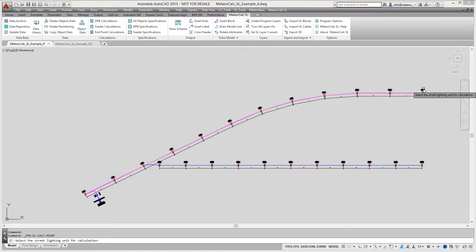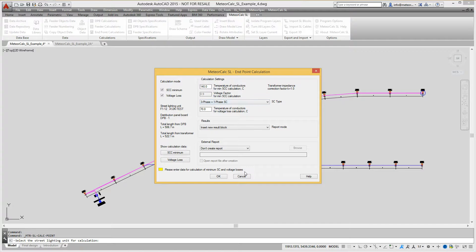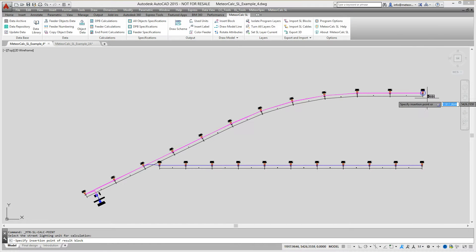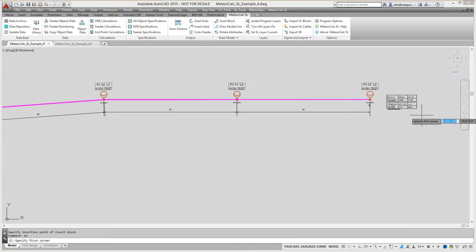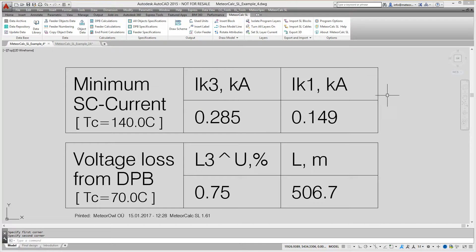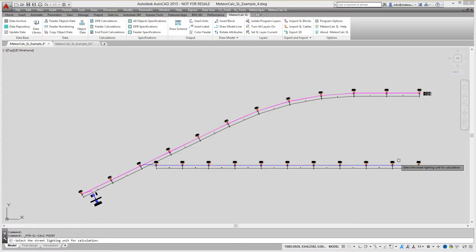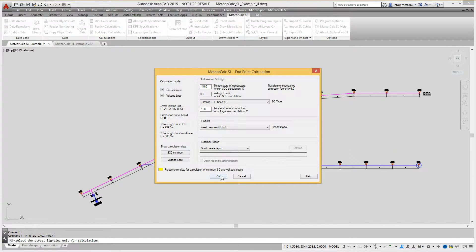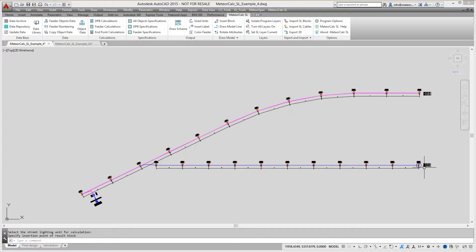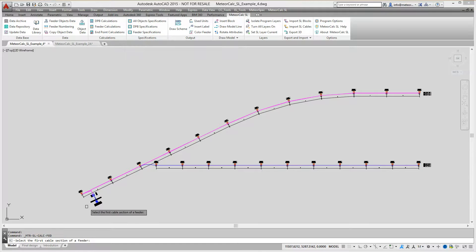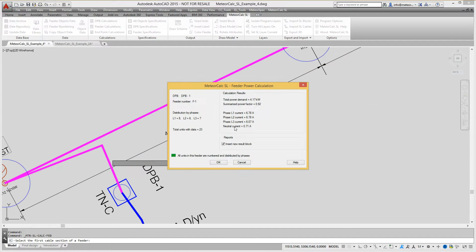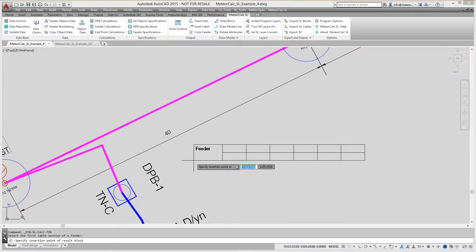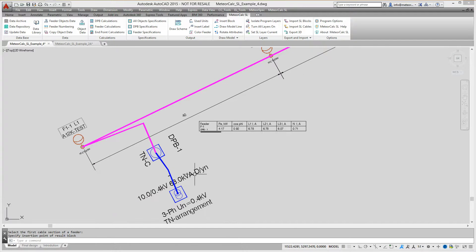First, we do the calculation at the endpoints of the feeder. In the dialog window, we can change the basic parameters of the calculation and select the result output mode. By default, the calculation results of short-circuit currents and voltage losses at the selected endpoints are outputted in a special block. We perform these calculations for all remote endpoints in the feeder. The next type of calculation is a calculation of feeder power sum and load currents in the feeder. The calculation of load currents is performed separately for each phase and for the neutral conductor. The calculation results are outputted in a special block.